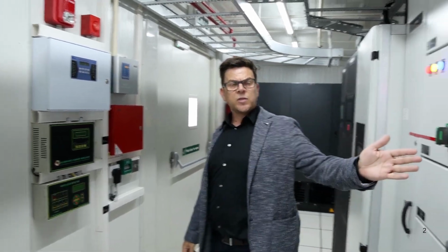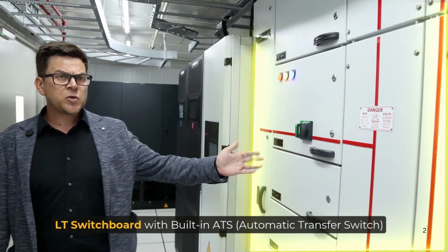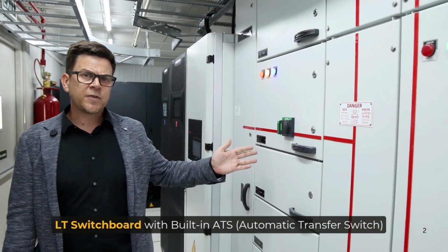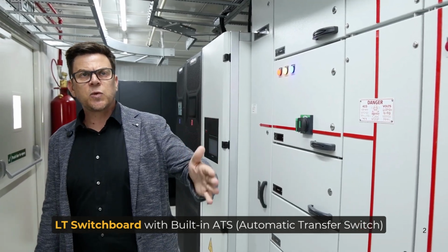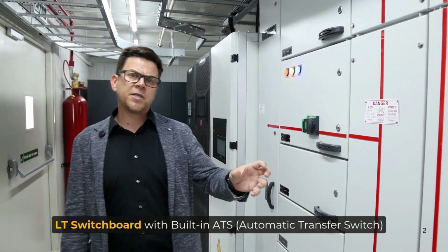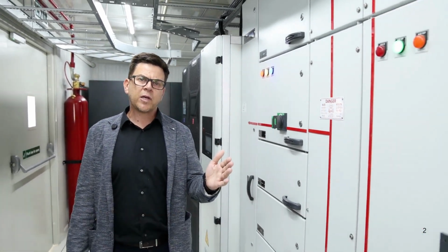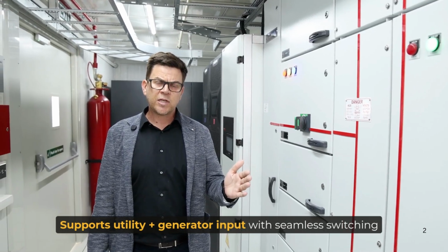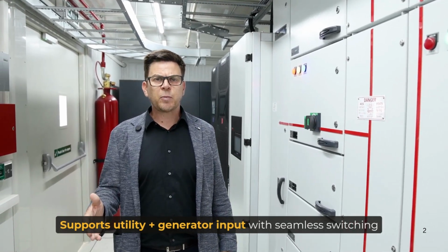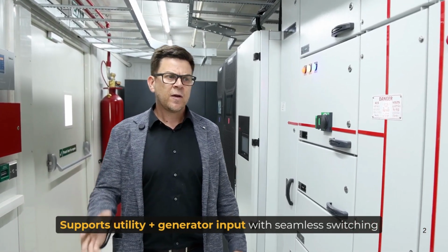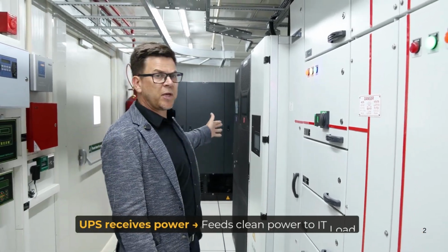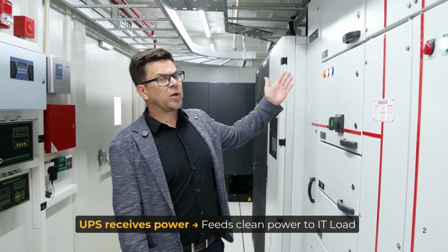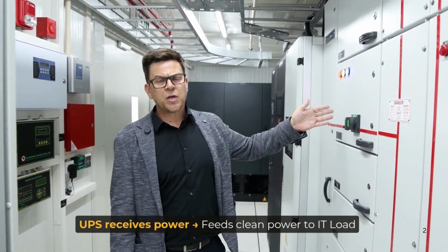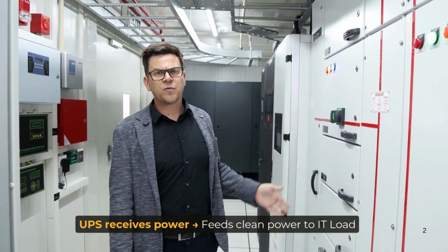And then this is all supplied and fed into the LT switchboard that we have on the left-hand side over here. Essentially, this switchboard is set up with a built-in ATS bringing in your main power connection from the utility supply, as well as the generator supply, and you can transfer over from there. You have supply of power to the UPS, and the board is then integrated to bring back the UPS-supplied power, which then goes out to your IT load downstream from there.